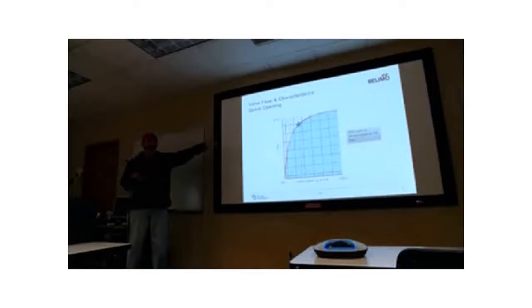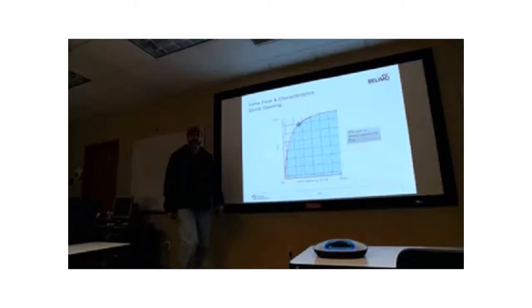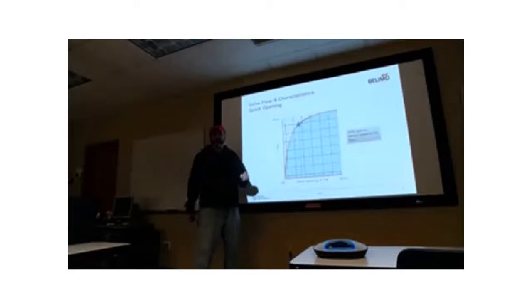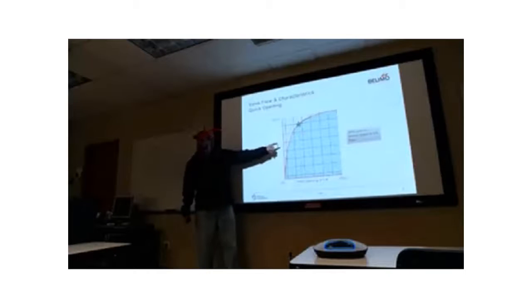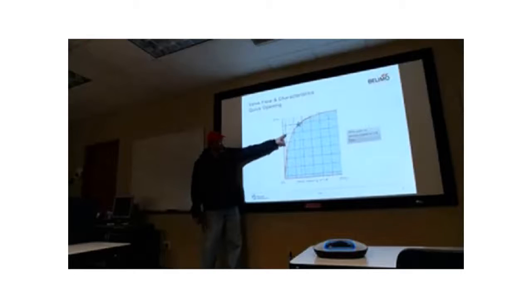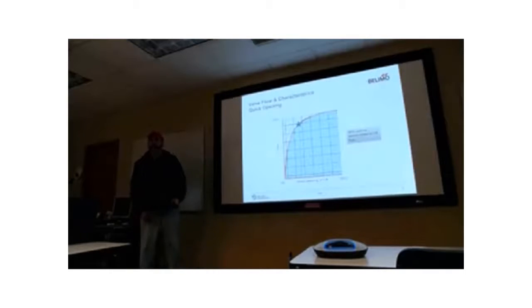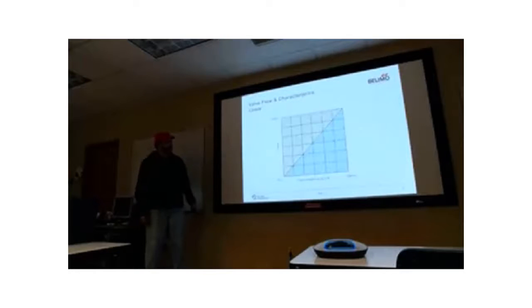So what would this work best for? On-off control. Yeah, exactly. Two-position, boiler isolation, chiller isolation, heat pump isolation, right? Just water on, water off. What it wouldn't be good for is what? Trying to modulate, exactly. Look how steep that curve is, right? You move that valve just a little bit, you get a huge change in flow. That's really hard to control. So yeah, two-position control and quick opening go together.